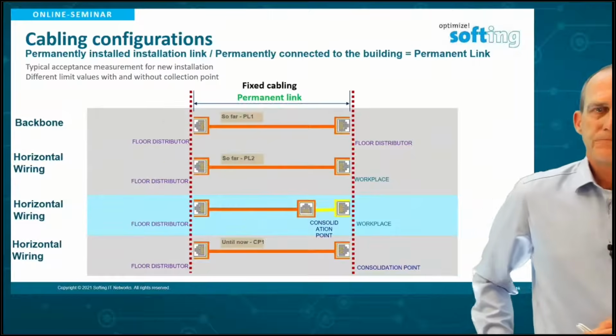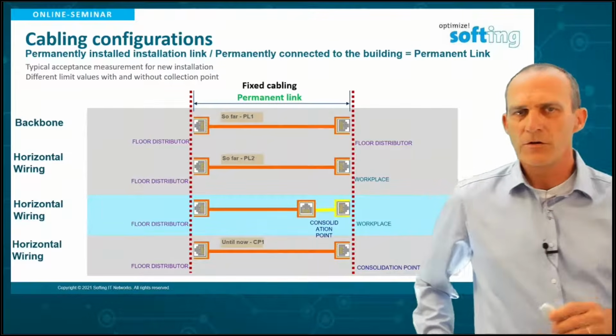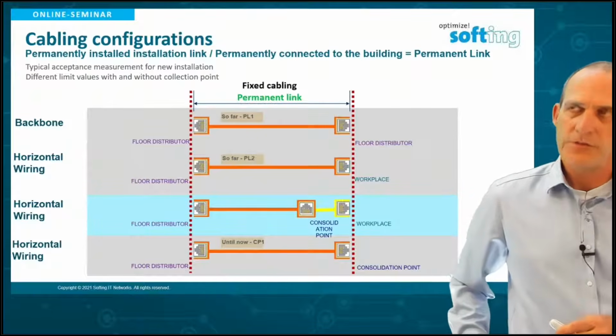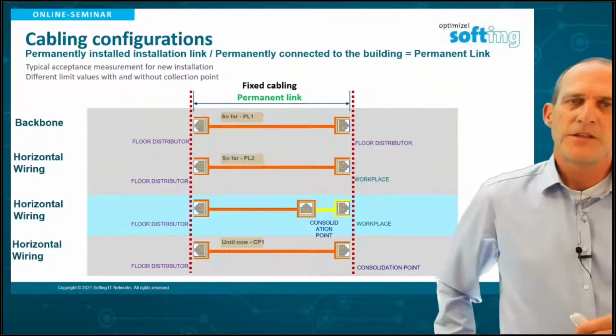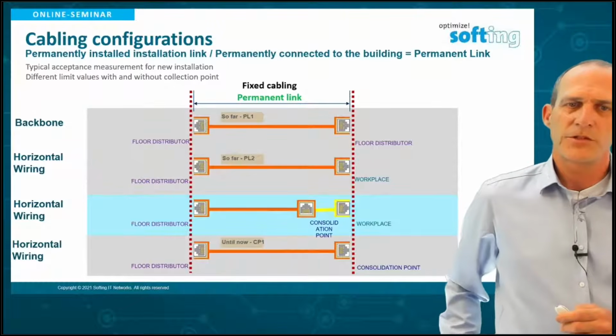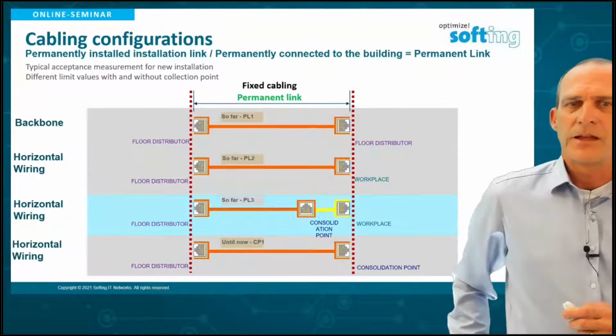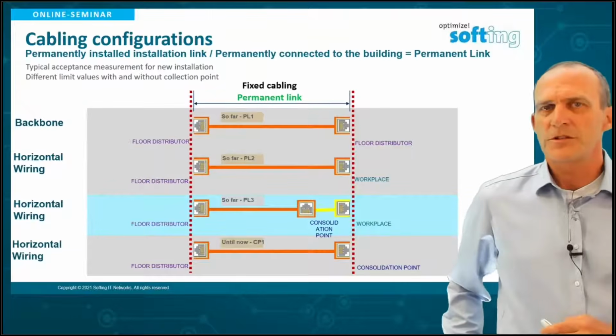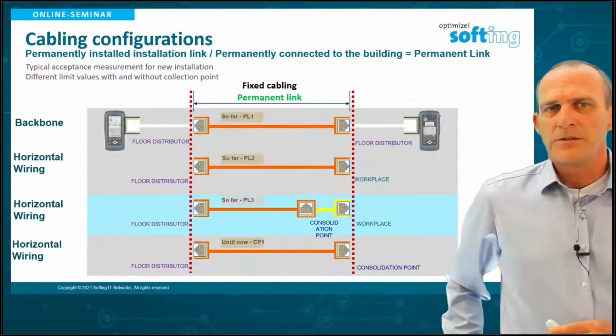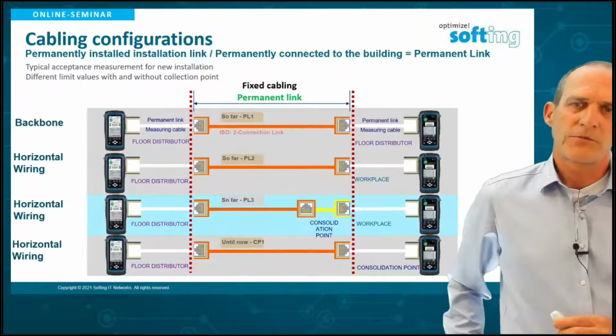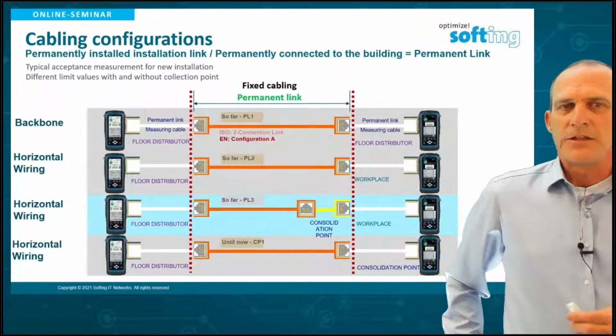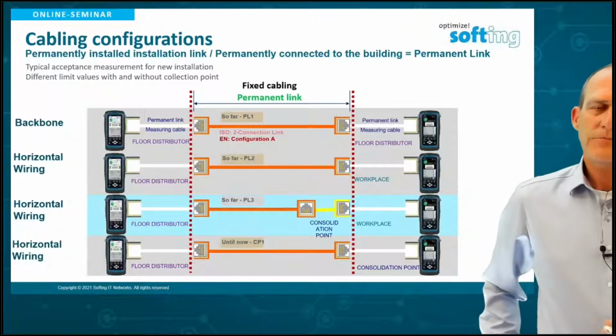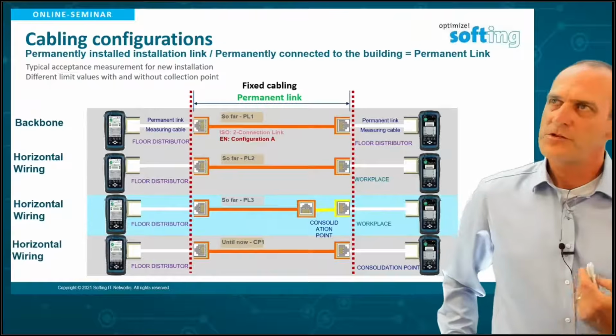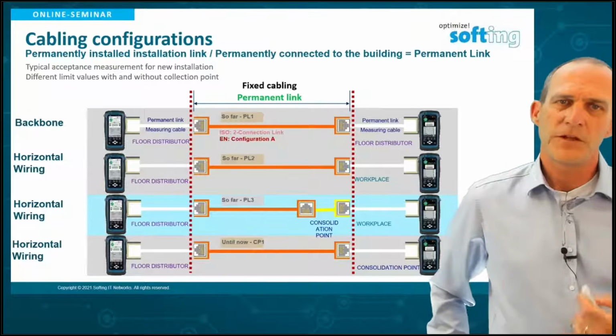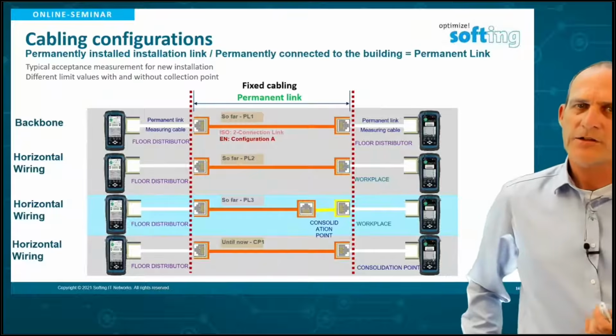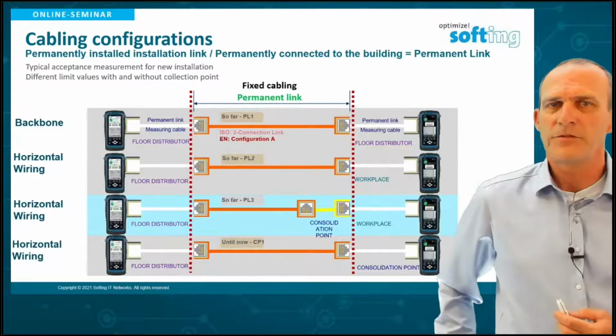In the past, in the old versions of EN 50173 and ISO 11801, these configurations were called PL1, PL2, or CP1, and the one up to the consolidation point was called PL3 - measured with cables, of course. In the new configurations from 2018 on, PL1 is now called a 2-connector link in ISO, and configuration A in EN.